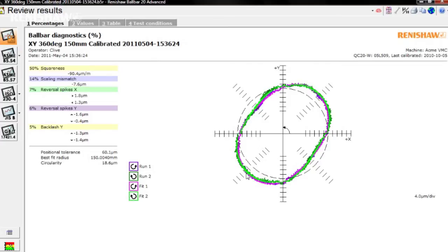The positional tolerance value, which appears only if you have performed a calibrated test, is equivalent to the positional tolerance value found on engineering drawings, and can therefore be used to estimate if a machine is able to produce parts to the drawing tolerances.